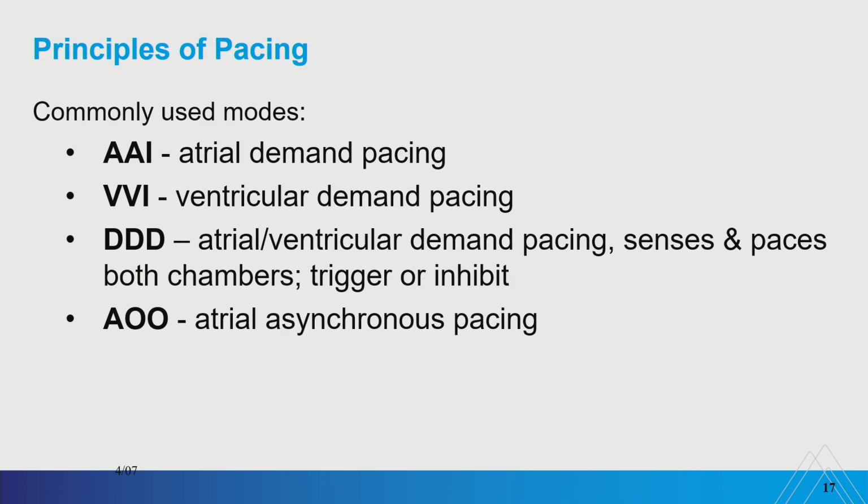It's 1 second. Okay, so the pacemaker is waiting. There is no QRS within 1 second. What does it do? It atrially paces. Hopefully there's a P wave. That atrially pacing will set off the secondary clock to count down 170 milliseconds. Again, that can be changed. That's the default on the pacemaker. After 170 milliseconds, if there is no QRS, it will ventricularly pace. Hopefully there's a QRS. That will reset the primary clock to start counting down 1 second from that point on again, and so on. If there's no QRS, it will atrially pace.